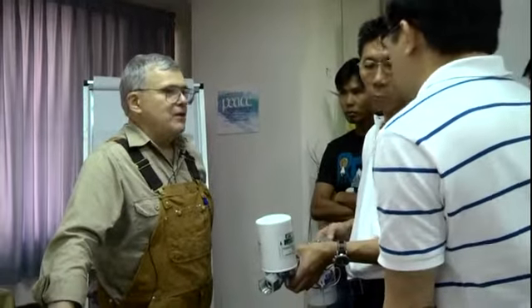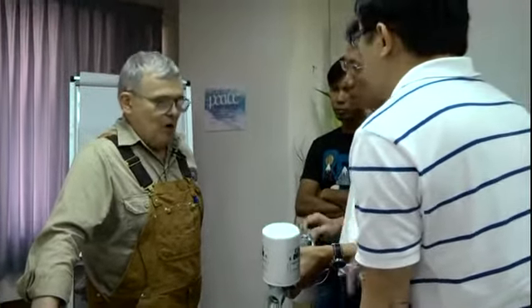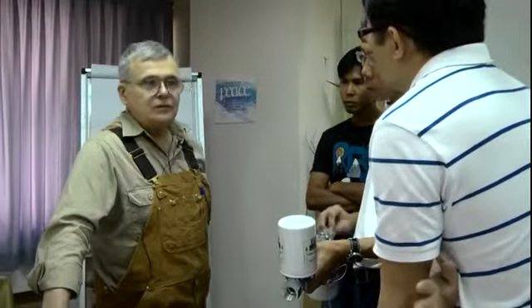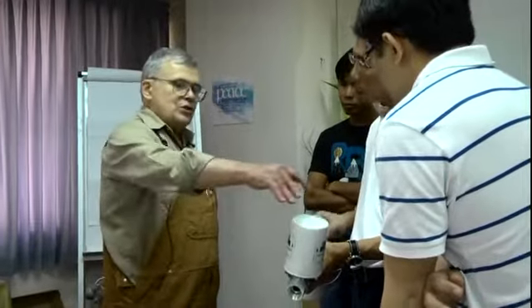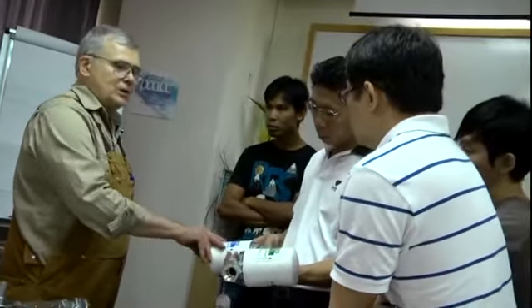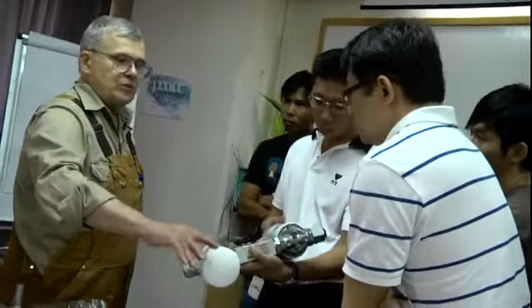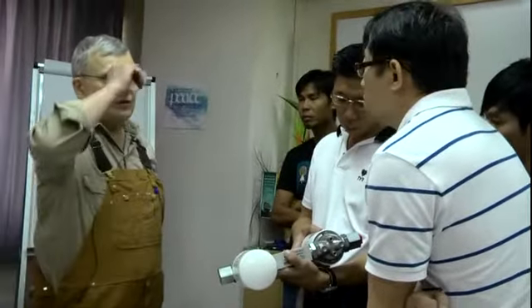So internally they are the same. Exactly the same. Identical structure, all three of them. They're a combination flow homogenizer and pulsation damper. We're using this one only as a pulsation damper, and this one only as a flow homogenizer. We don't care about the turbulence in the fuel once it leaves our sensor.